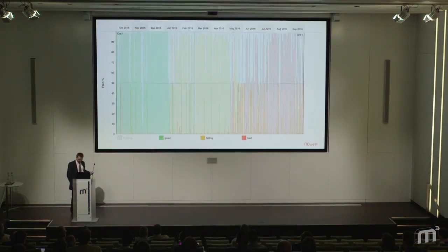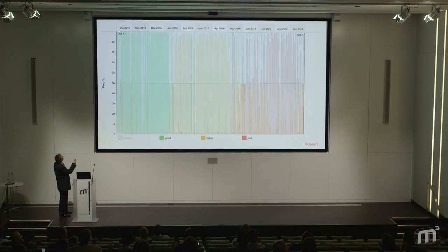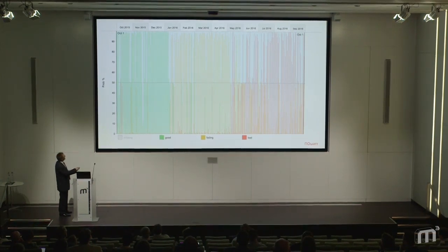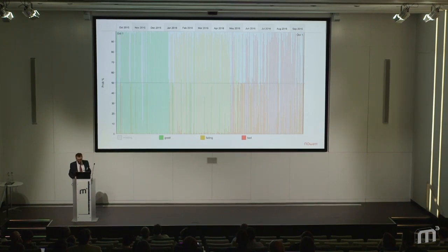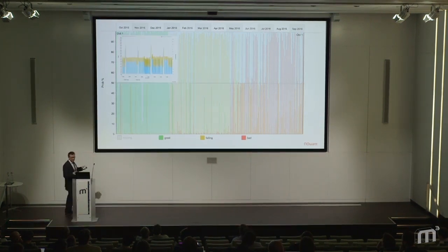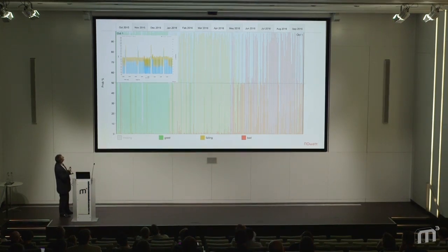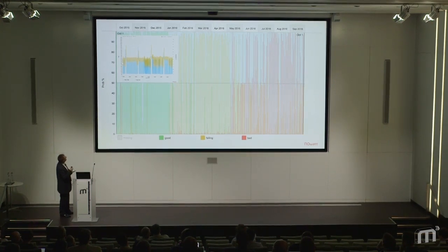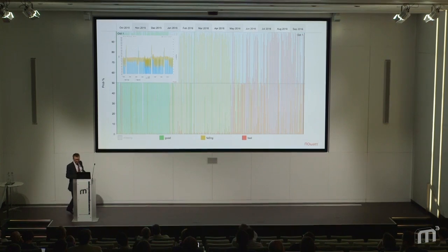Let me show you our AI analysing a chiller over 12 months to give you an example. So this is one chiller over 1 year. At the beginning of the year, I'll start on October 1, the AI is predicting with over 90% confidence, it's seeing good patterns. Things are cool. And if we look at the pattern, which we wouldn't normally do, we can see, yeah, we agree. The temperature is acting in synchronization with the condenser operation. The temperature's cool. It looks pretty good.